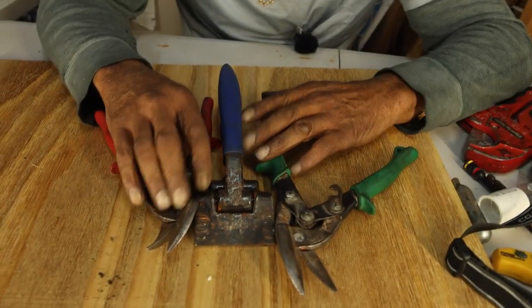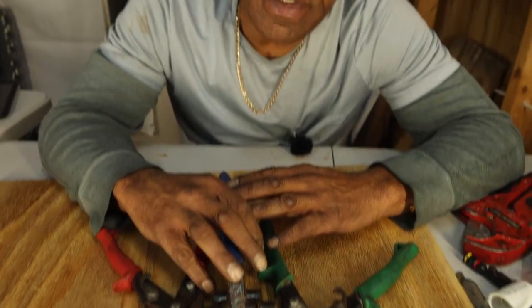Rights cut to the left, lefts cut to the right. I'm not teaching you guys to be sheet metal workers, but if you go on a job and you find the existing A coil has a leak in it and cannot be repaired, its only fix is to be replaced. In order to do that, you very well may have to make some adjustments to the ductwork. Now, for that, I'm ultimately going to recommend in the beginning that as you get into the industry, you make friends with other tradesmen that you meet in supply houses. Get their phone numbers. Find out guys that do ductwork.